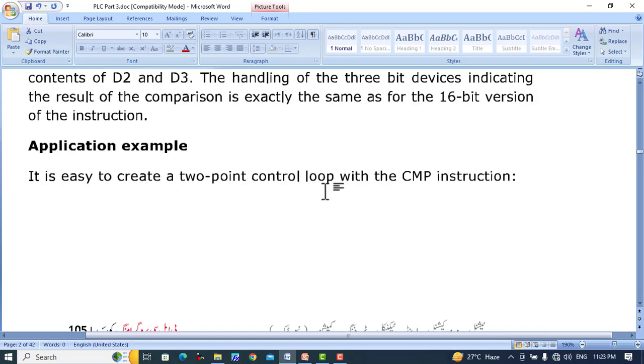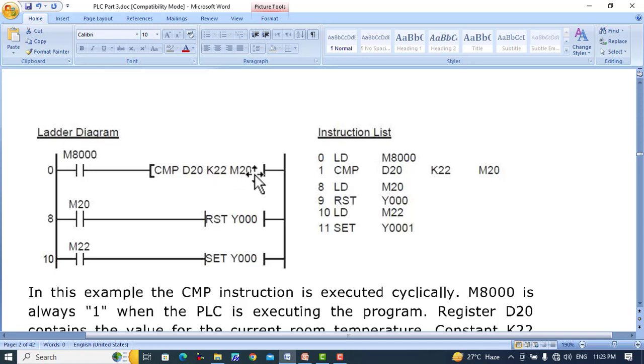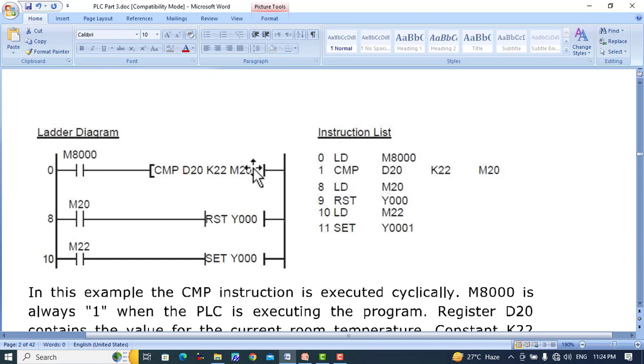It is easy to create a two-point control loop with the CMP instruction. M8000 is a special relay that is always on when the PLC is in the running state. A CMP comparison of D20 and K22 is made with this command, and the results are stored in M20, M21, and M22. When D20 is greater than K22, the result is stored in M20. When D20 is equal to K22, the result is in M21. When D20 is less than K22, M22 is set to one.